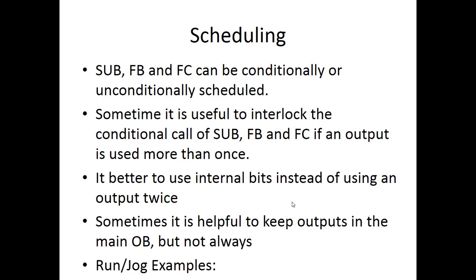Subroutines can be conditionally or unconditionally scheduled. A lot of times subroutines are just unconditionally scheduled — they just automatically run to organize your code. Sometimes it's useful to interlock these so that you're not calling both at the same time, calling one or the other. That would be good if an output is used more than once, though I don't recommend using an output more than once. It's better to use internal bits instead of using an output twice.